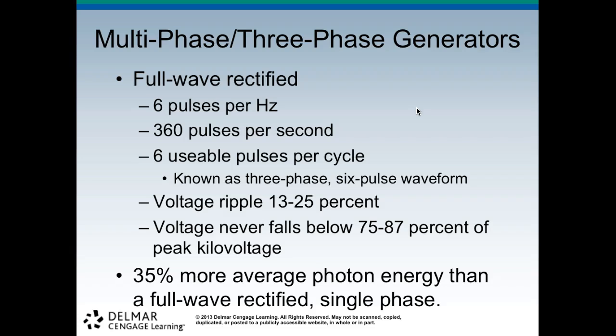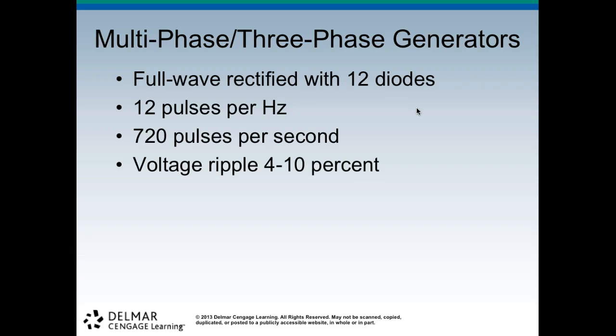So with multi-phase, 3-phase generators, full wave rectified, we have 6 pulses per hertz, 360 pulses per second, 6 pulses per cycle, known as the 3-phase 6-pulse waveform. So the voltage ripple is 13 to 25%, and the voltage never falls below 75 to 87% of the peak kilovoltage. So 35% more average photon energy than full wave rectified single phase. So multi-phase, 3-phase generators, full wave rectified 12 diodes: 12 pulses per hertz, 720 pulses per second, and voltage ripple is 4 to 10%. And in your Carlton book, they don't talk about this 12 diode, so just be aware.